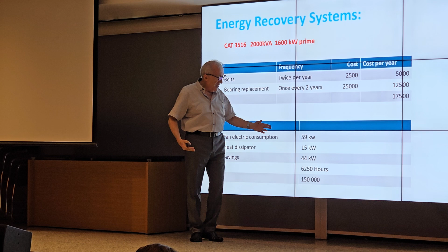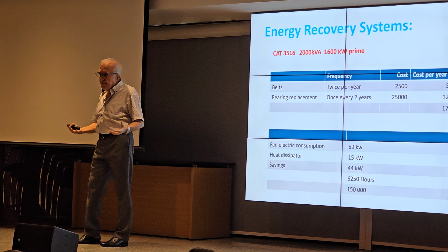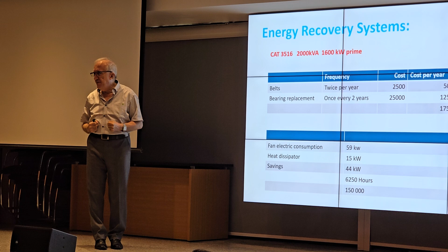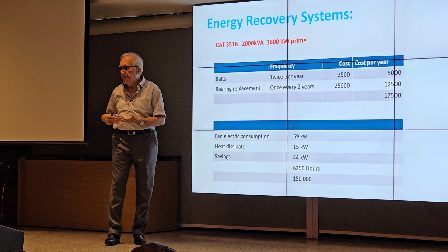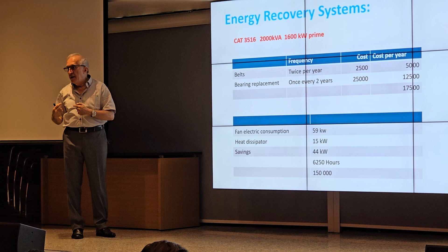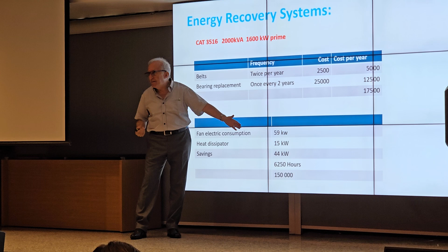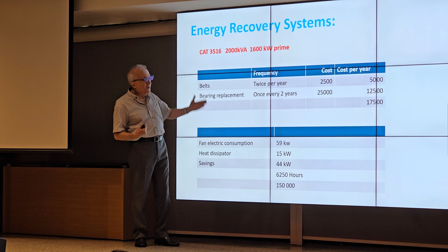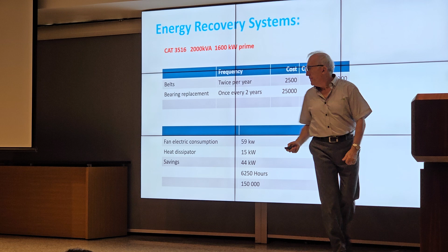And it seems it's why the manufacturer is not using a remote radiator like the one we are using, because these generators are meant to be compact, and they have a small radiator with a very powerful fan. They are either compact or installed on a tractor or whatever, so they are meant to be used as backup. If we are using them as a backup generator, it will run for 100 hours a year maximum. But in our case in Lebanon, we are running this almost all the time, so the saving is huge.